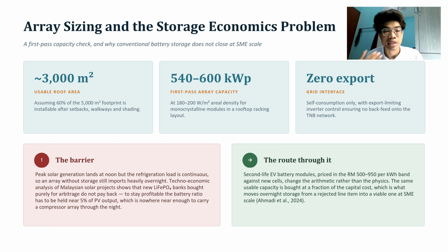So the obvious answer is to add batteries. But normal new batteries are actually too expensive to make financial sense for this purpose. Studies show that if you only use batteries this way, they should stay under about 5% of our solar output to remain worth the cost. This is nowhere near enough to run our compressor overnight. So instead, we use second life batteries that were used in electric cars before and are now sold at a much lower price, around 500 to 950 per kilowatt hour, instead of buying completely new ones. Same amount of storage but much lower cost. So this will make overnight battery storage actually realistic for SME businesses.